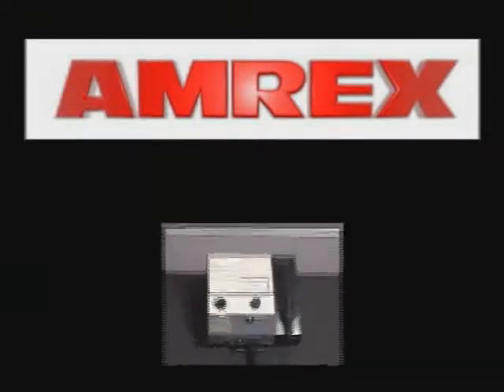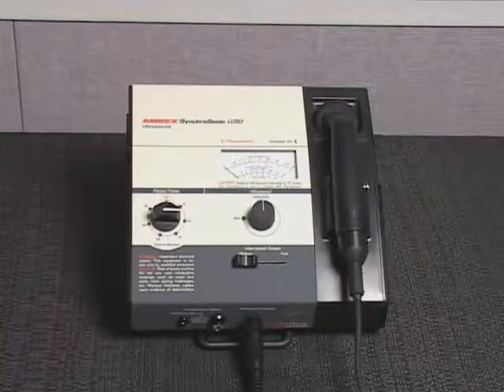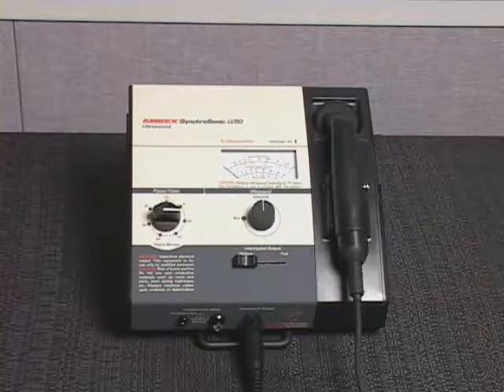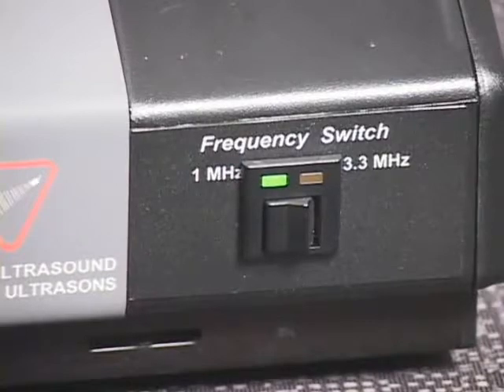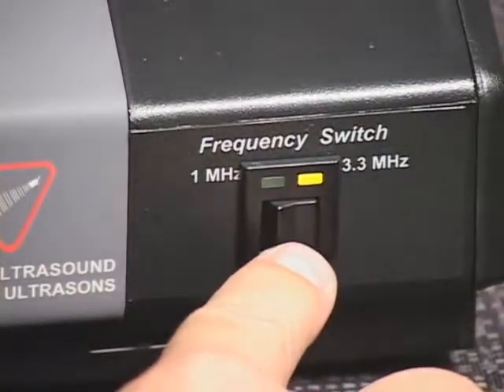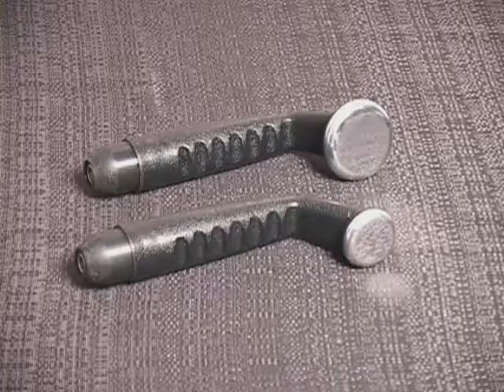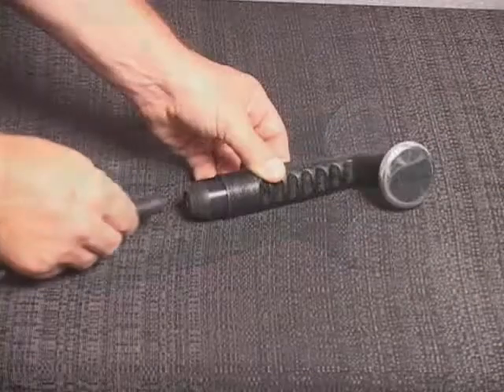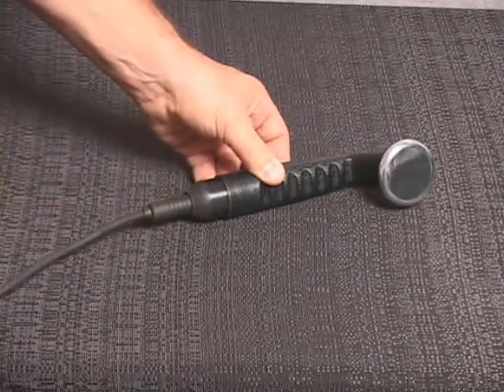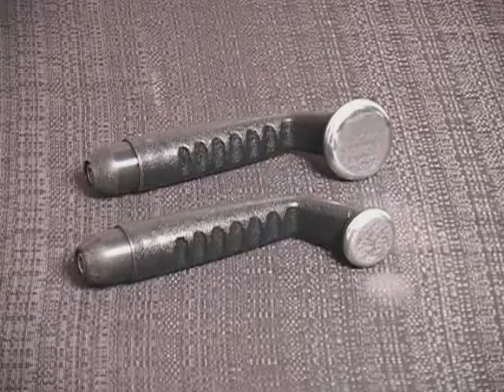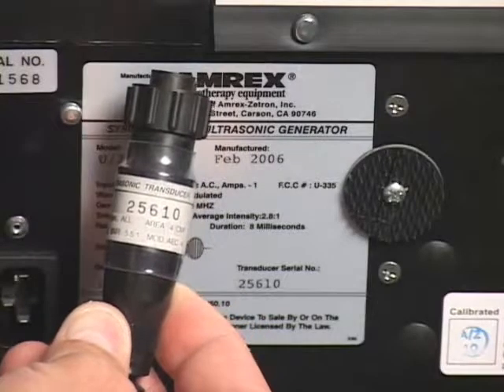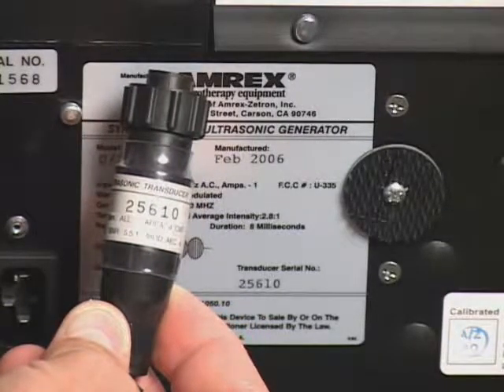U50 general operation. Amrex model U50 has a standard output of 1 MHz frequency. Amrex does offer both 1 and 3.3 MHz outputs as a device option. Other U50 device options include a small faceplate transducer, quick connect detachable cable transducers for easy cable replacement, and dual transducer equipped ultrasound generators. U50 generators are equipped with serialized transducers. The transducer or transducers assigned to a given generator must only be used with that generator.